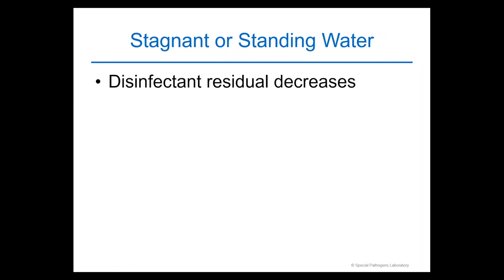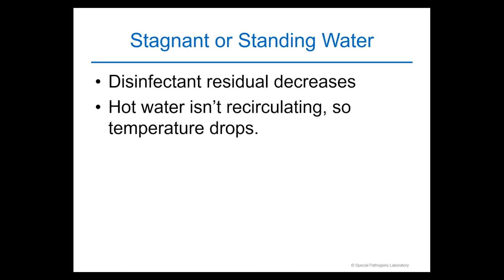Because when that water stagnates, disinfectant residual disappears. When hot water isn't recirculating, its temperature drops into that sweet spot for bacteria to grow. Similarly, cold water sitting in those lines warms up, again right into the sweet spot for Legionella and other waterborne pathogens to grow.